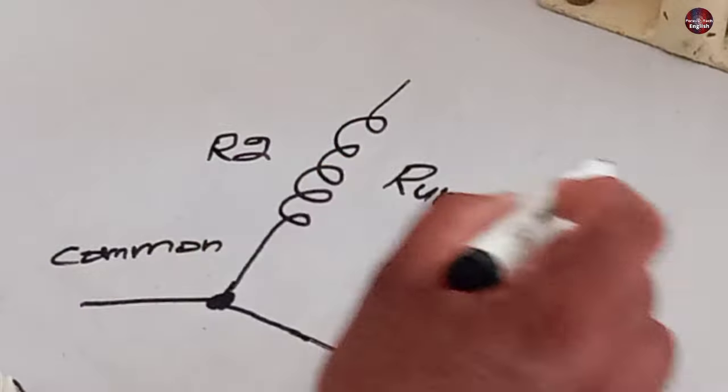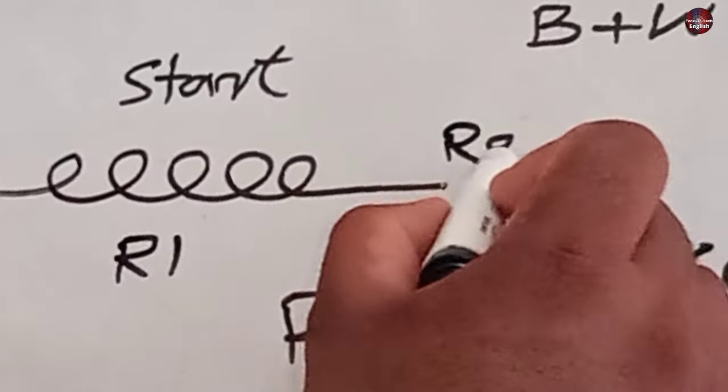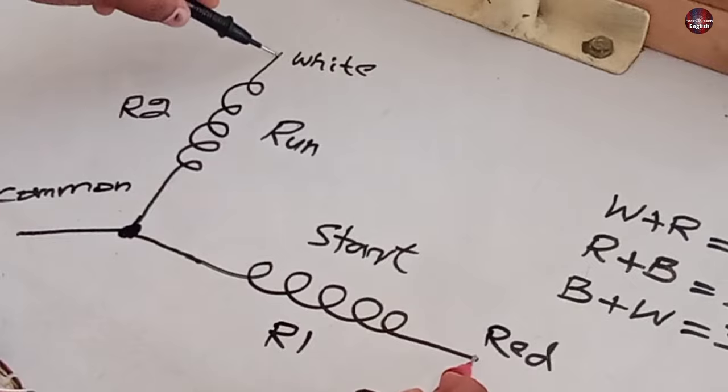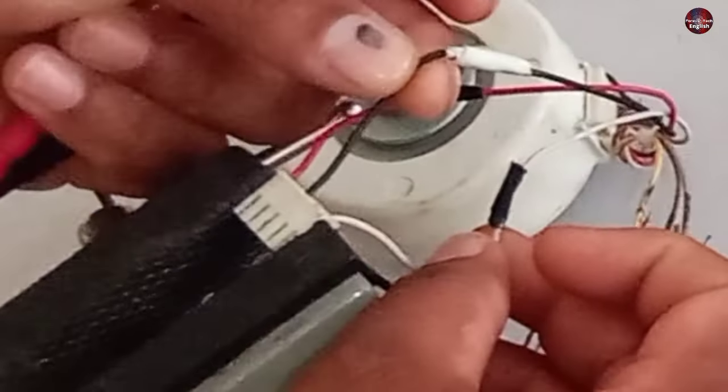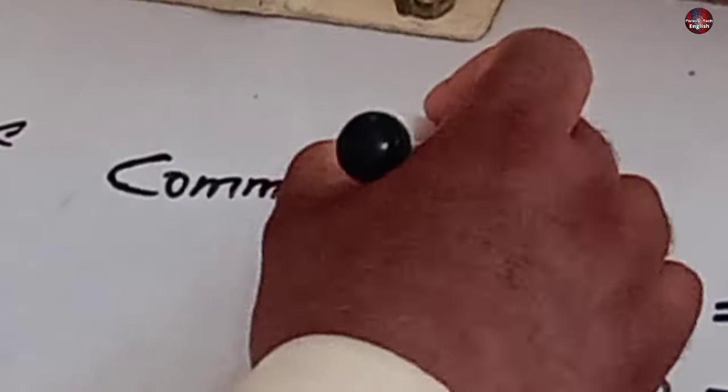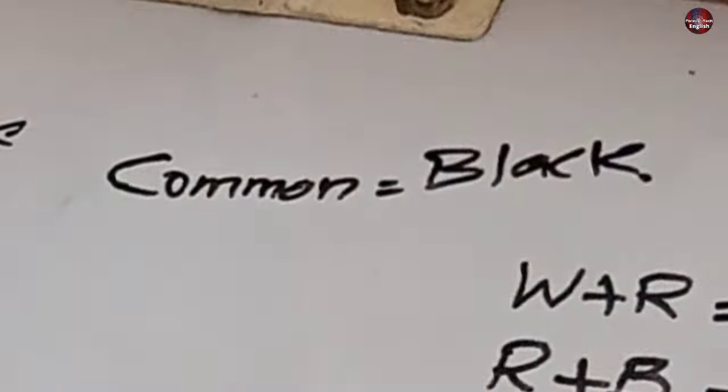Now I will name run or R2 as the white wire. The R1 is the red wire. We are getting this value when I connect the multimeter probes with these wires. It means the one wire which is left is the black wire, which is the common wire. I am writing it as well that the black wire is the common wire.